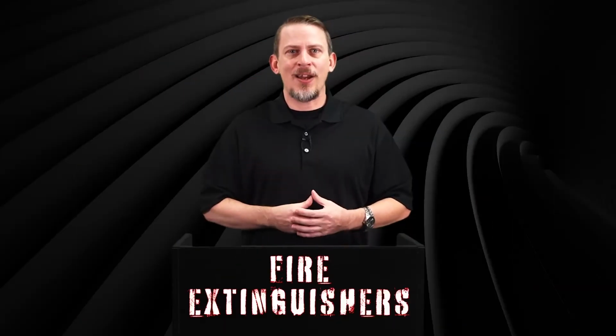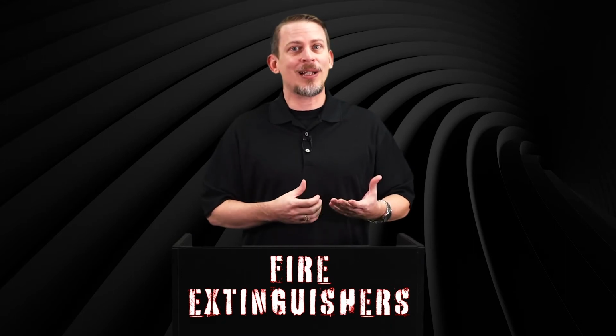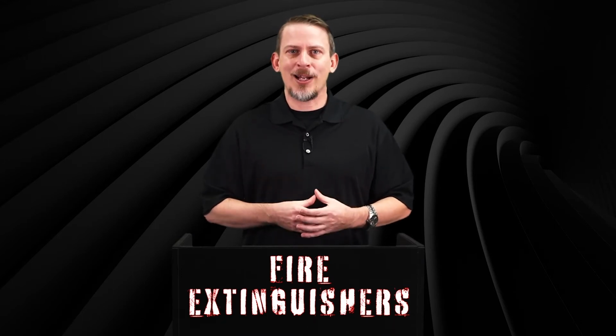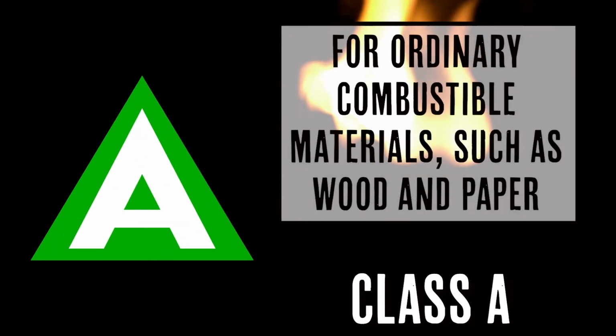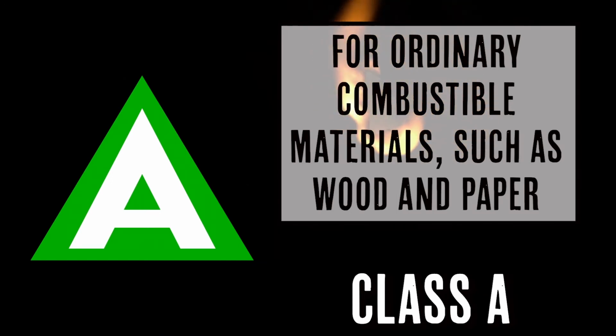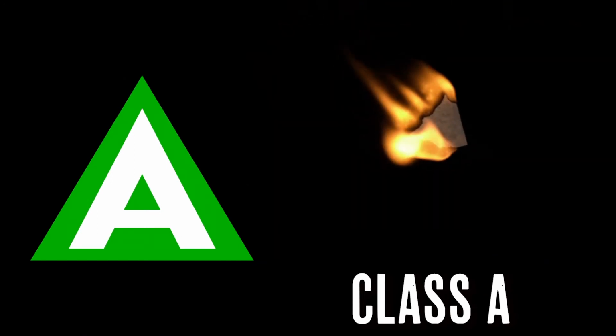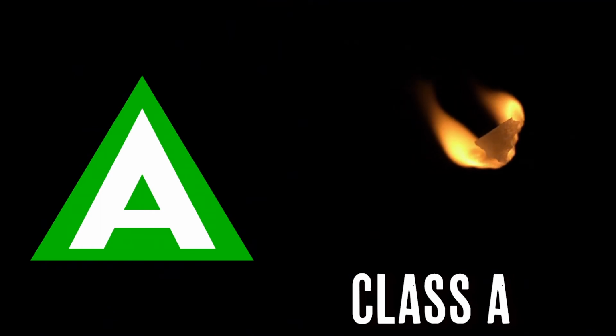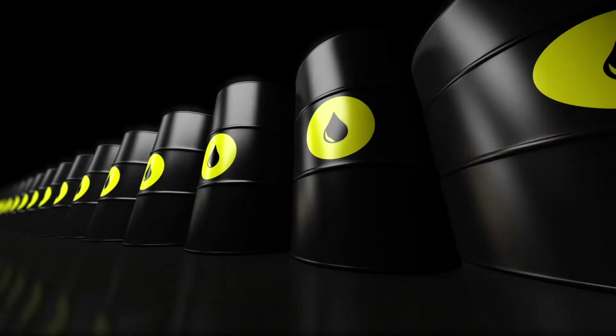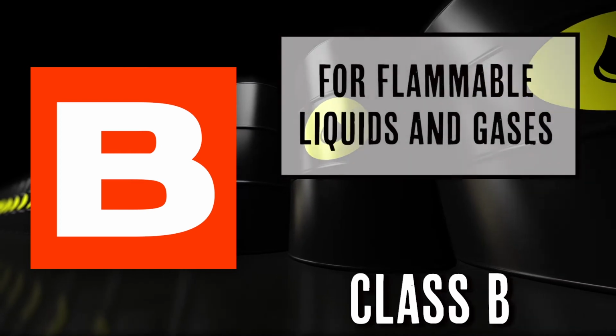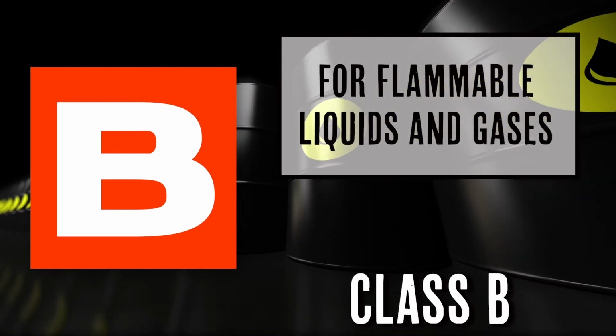There are also classifications of fire extinguishers that help you determine what kind of fire the extinguisher is meant for. Pay particular attention to the different classifications so you will always have the correct extinguisher in the right location. Class A, for ordinary combustible materials such as wood and paper, like you'd find at a pallet production facility or where there are large amounts of paper. Class B, for flammable liquids and gases such as gasoline, diesel, or any other type of gas in a compressed cylinder.